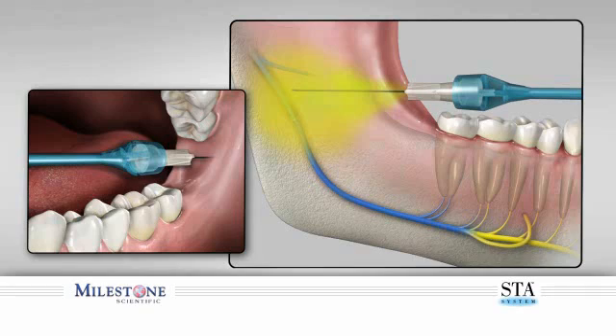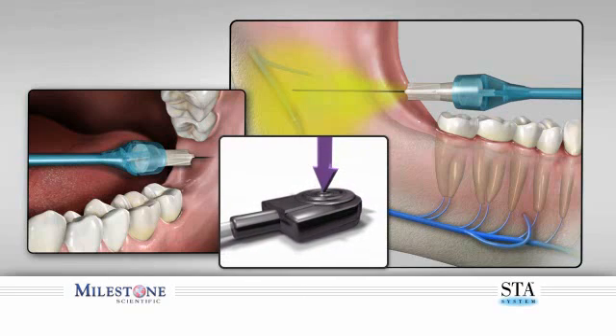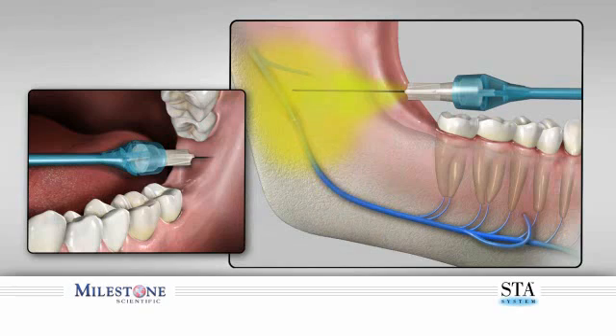Continue the injection by depressing the foot control pedal. It is recommended that the first quarter of the cartridge be dispensed using the control flow rate before you transition to the second, faster rapid flow rate. The rapid flow rate is used during block injections only after your patient has acknowledged that they have achieved soft tissue anesthesia of the area being injected. This is acknowledged by subjective statements elicited from your patient. When you have delivered the required dosage, you can remove the needle.